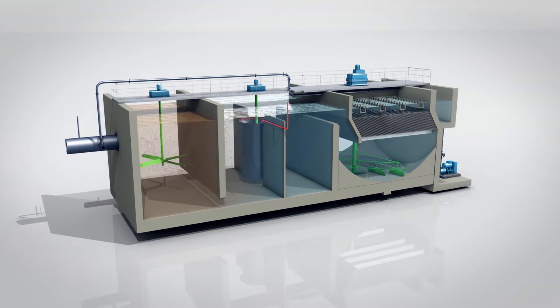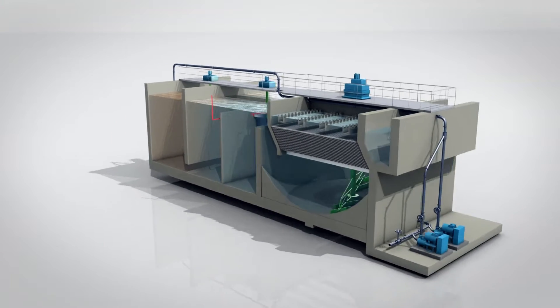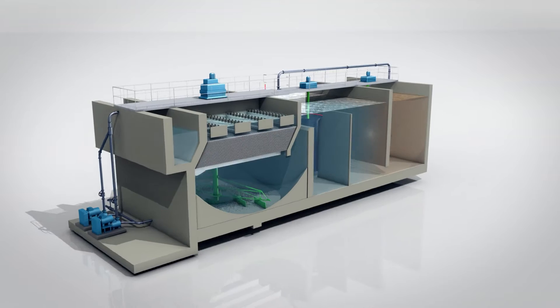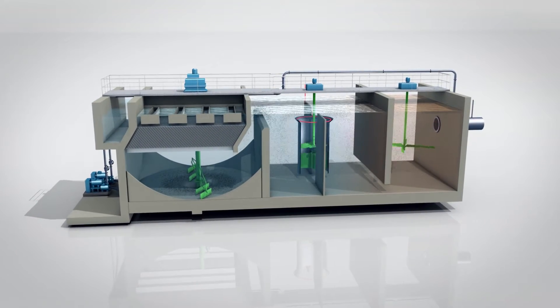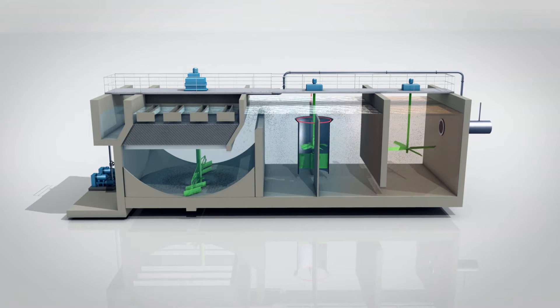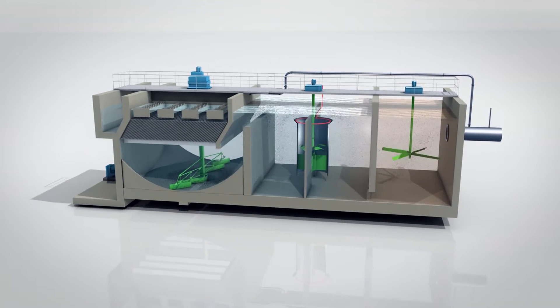Multiflo is a compact and fast-acting lamellar clarification process. Its principle: the water to be treated is coagulated using a metal salt-based reactive. Then the water is flocculated with a polymer in a tank fitted with Veolia Water Technologies' patented Turbomix System. The Turbomix System considerably shortens the flocculation time and accelerates the decanting rate.